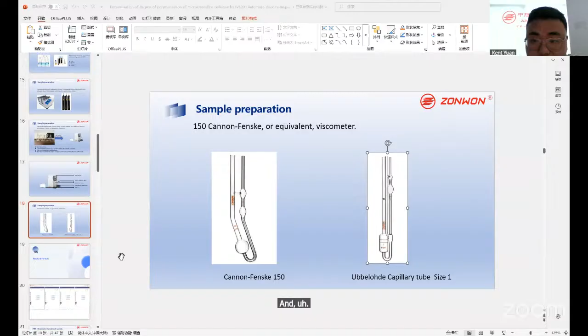So for this machine, when we do the testing, we need to make sure all the testing is correct, so we need to do the calibration. First, the calibration of the Ubbelohde tubes, the constant calibration. You can send it to a third party to get the certificate. The second calibration is temperature calibration. It is a water bath, and what is the bath temperature? Is it correct or not? So we can calibrate the water bath temperature precision. The third calibration is the digital thermometer. Because the digital thermometer precision is 0.01 degree, we can send this thermometer to a third party to do the calibration and get the certificate.